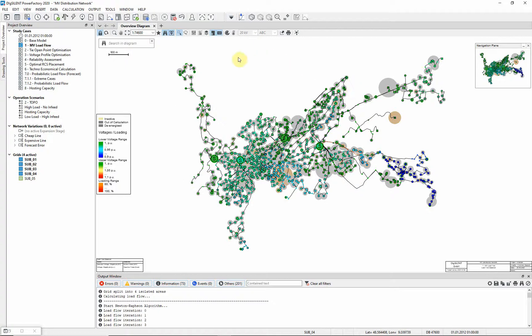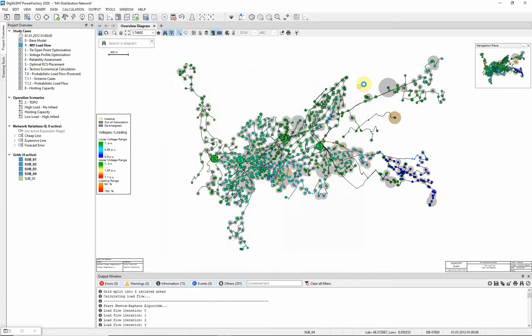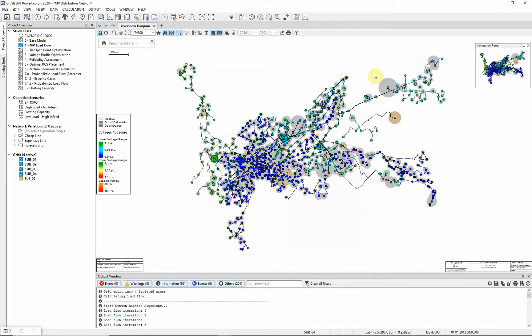Now, leaving the load scaling at 150%, we will switch off the automatic tap adjustment of transformers. Execute the load flow. It can be seen that the voltage levels are significantly lower without the automatic tapping of transformers to improve the situation.